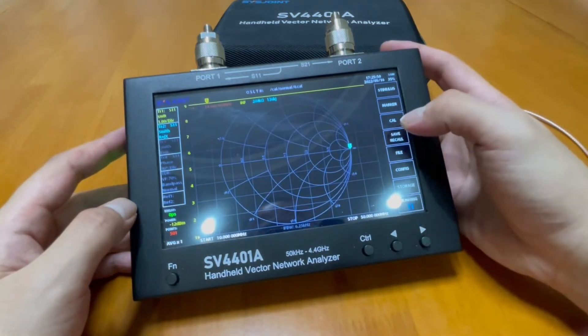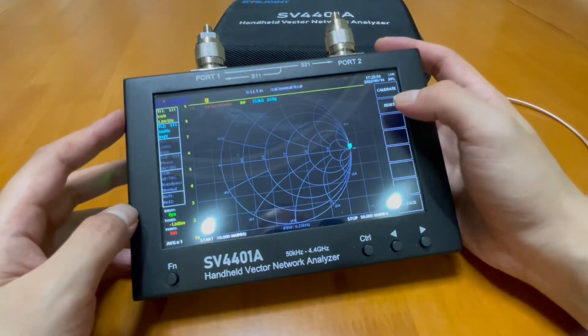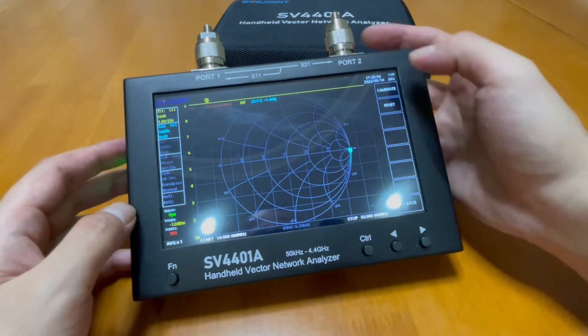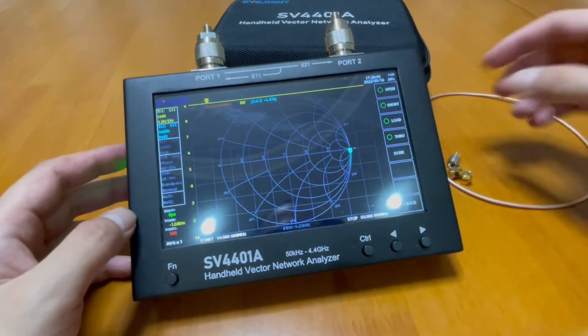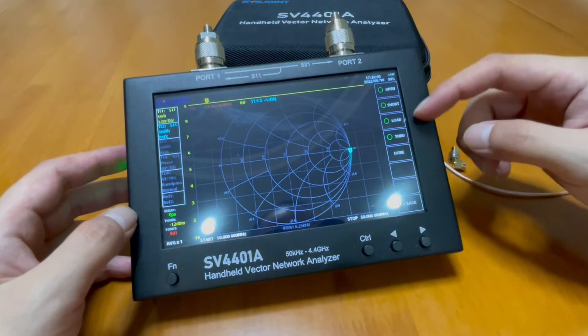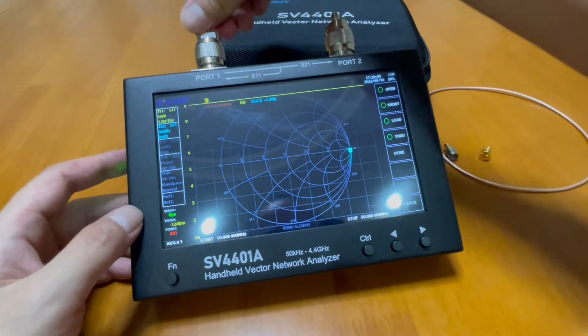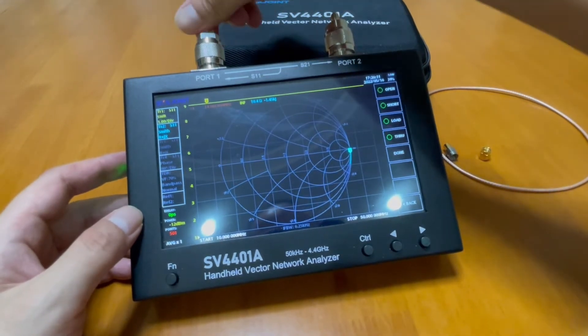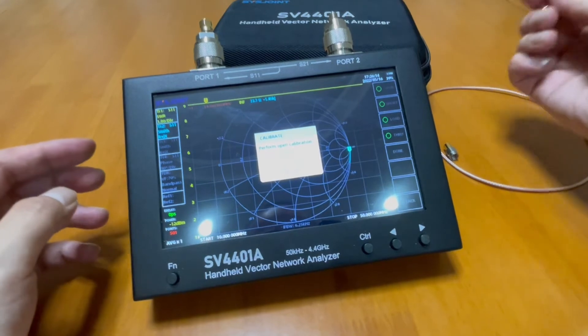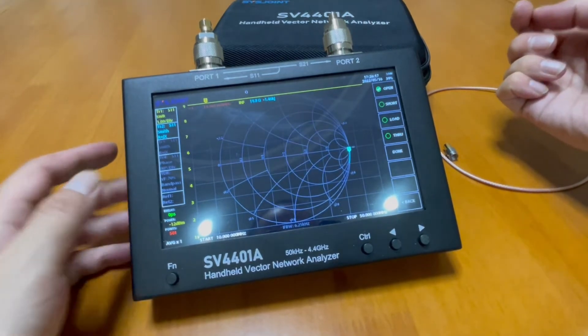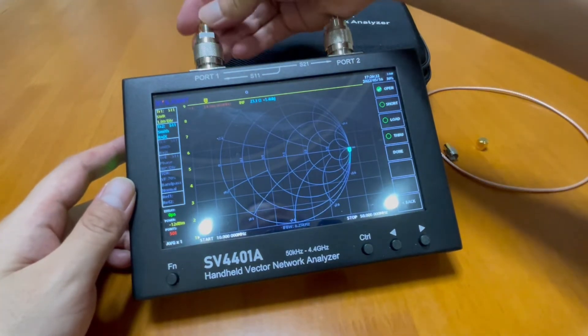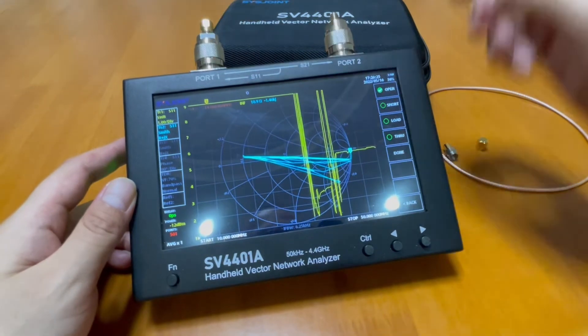We go back and we can start calibration by clicking on cal, which is calibration. Notice we need to click reset to make everything from zero again and calibrate. Now we're going to follow each of the options and do each of them. For the open, we put open to port 1 and click open, and same process with short and load. When you hear the beep, it means the process is done.